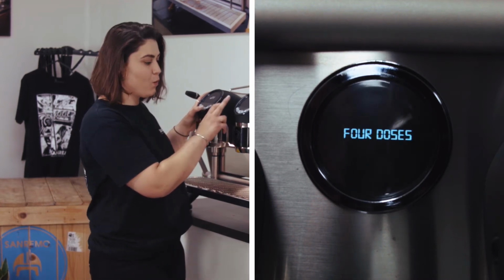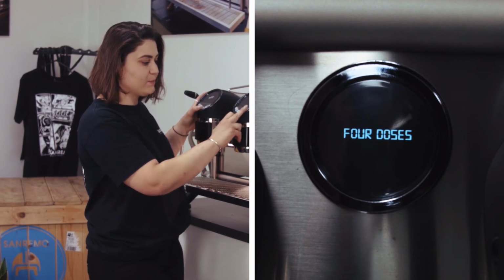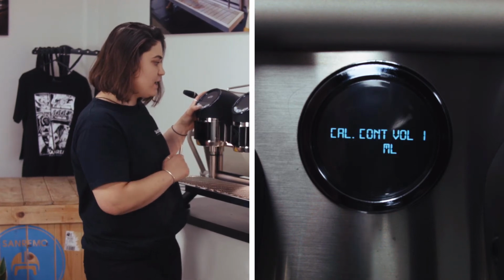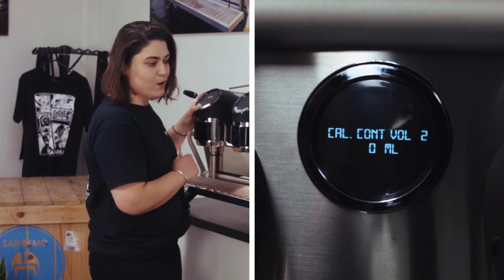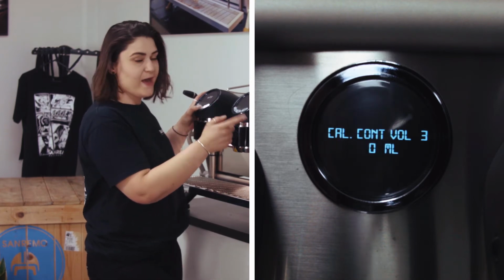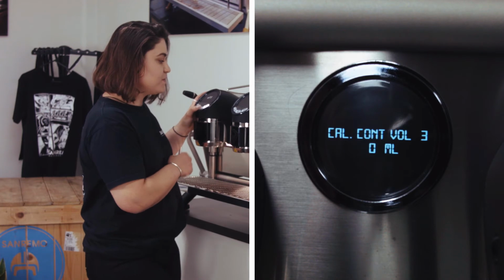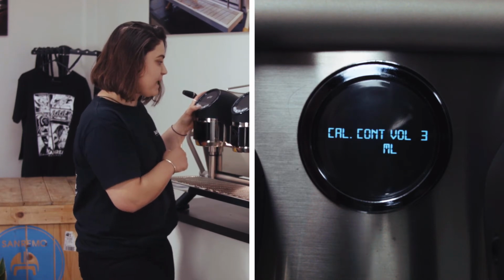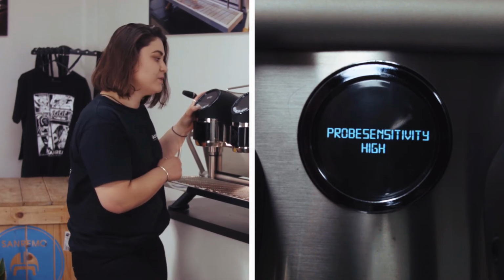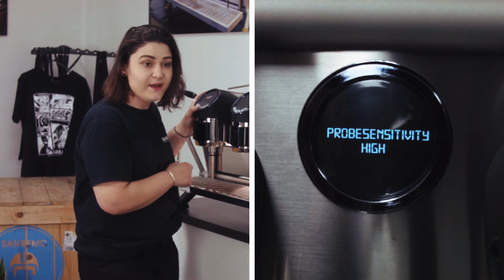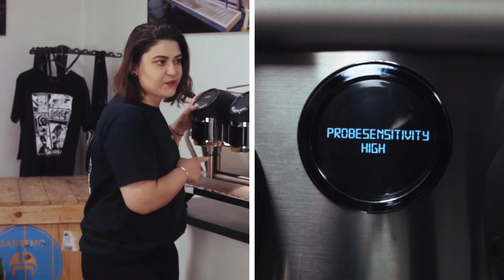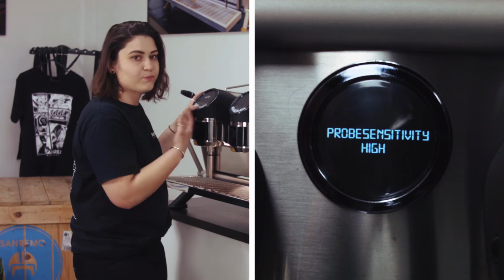Dose setting enabled, so your doses are all on. 4 doses, so you've got 1, 2, double tap 3, double tap 4. Enter. You've got offsets for your ml, so group 1, group 2, and group 3. If you need to put an offset, this is how you do it. Enter again, probe sensitivity. So probe sensitivity is normally set to high. We set this feature to high, so if you have really clean water, the probes just read a lot better.